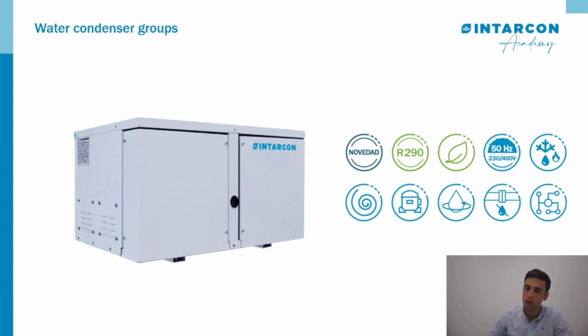This equipment, we are going to look at the details of this one. This is a water condenser unit designed for medium and low temperature applications. They are very compact and silent units that can be installed on the wall or directly on the refrigeration service, so you can adapt it to different situations. Their key features include a compact design, as I said, a hermetic reciprocating compressor or scroll compressor depending on the model, a condenser with stainless steel brazed plate, a refrigeration circuit with filter, pressure switches, safety valve. Also, we have a chassis of galvanized steel with sound absorbing insulation to minimize noise emission.